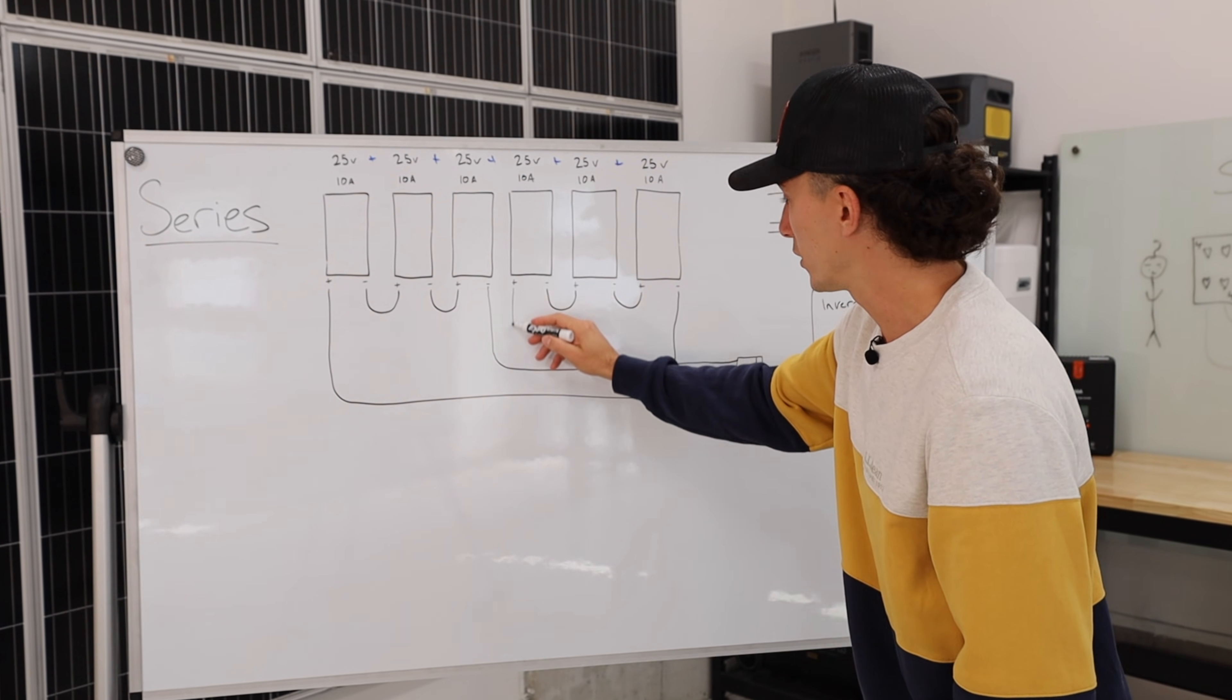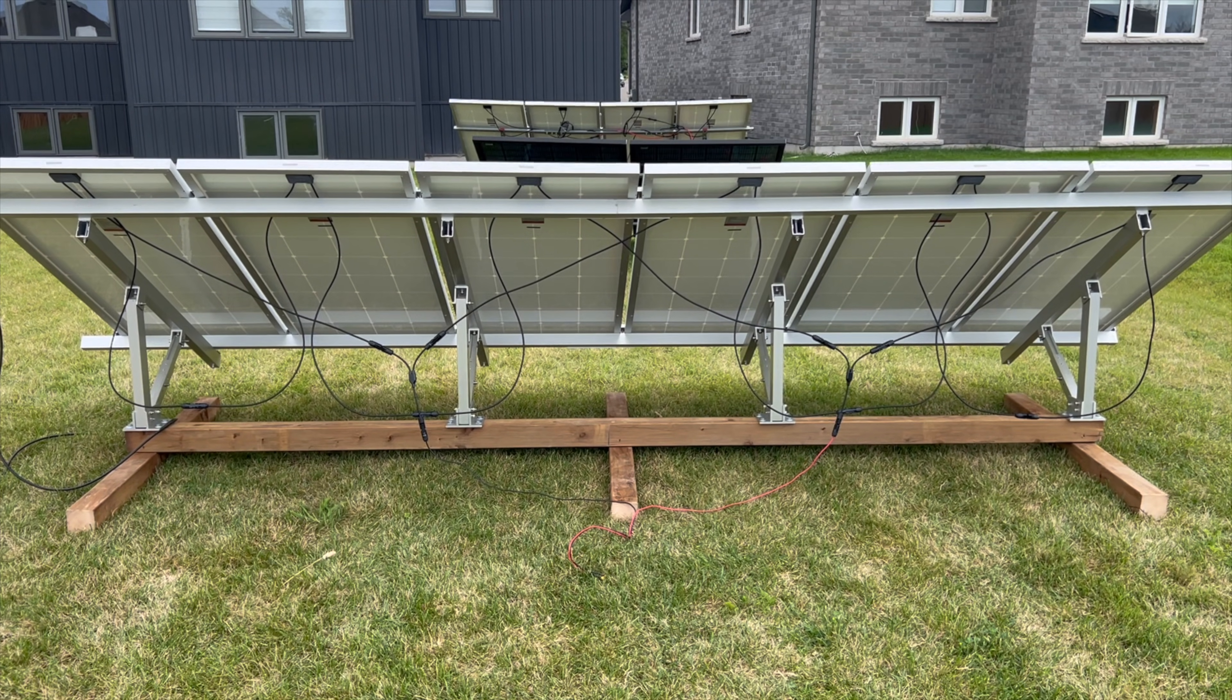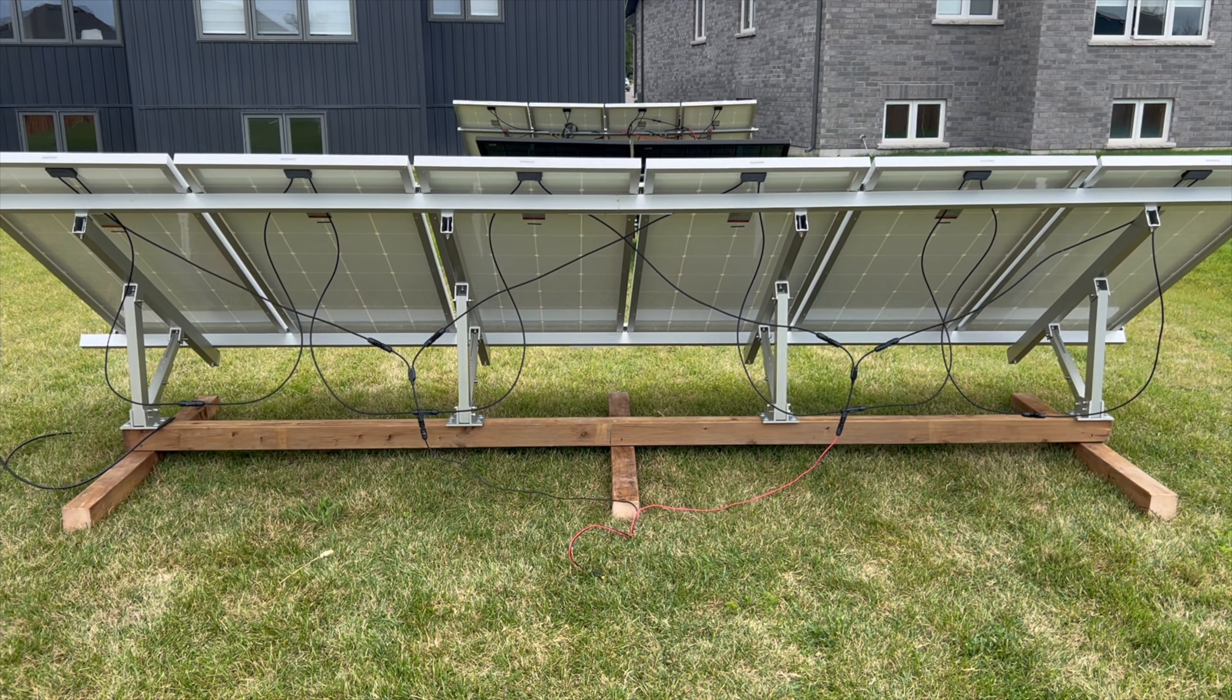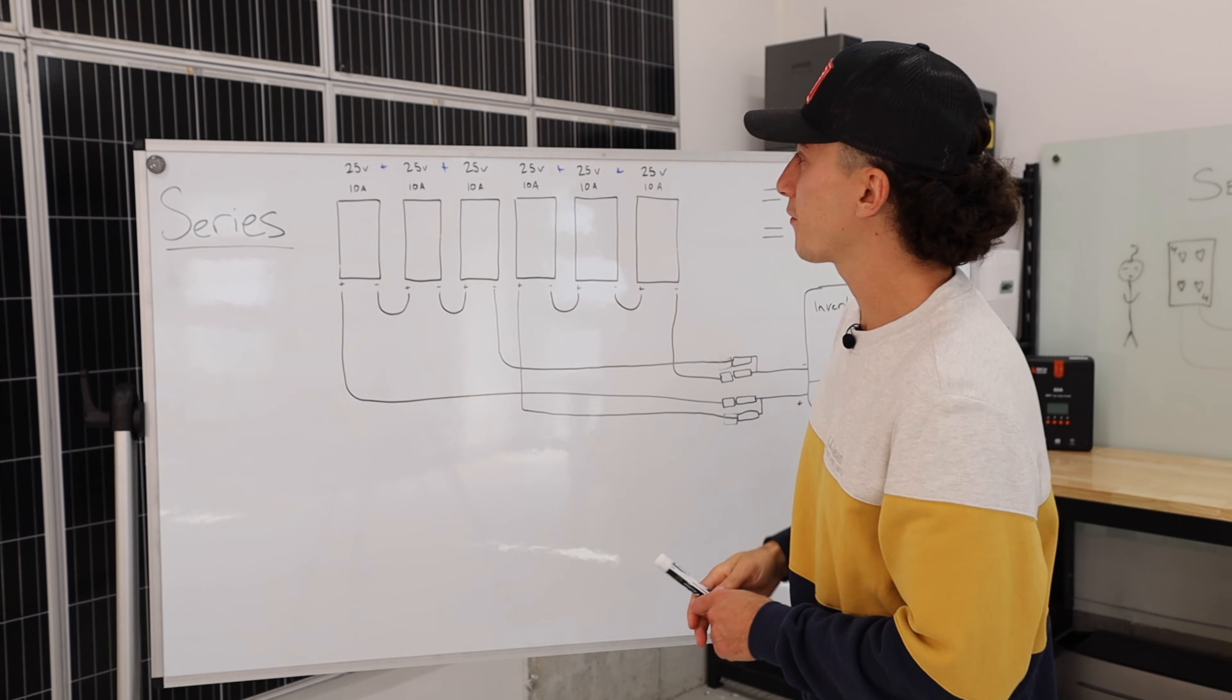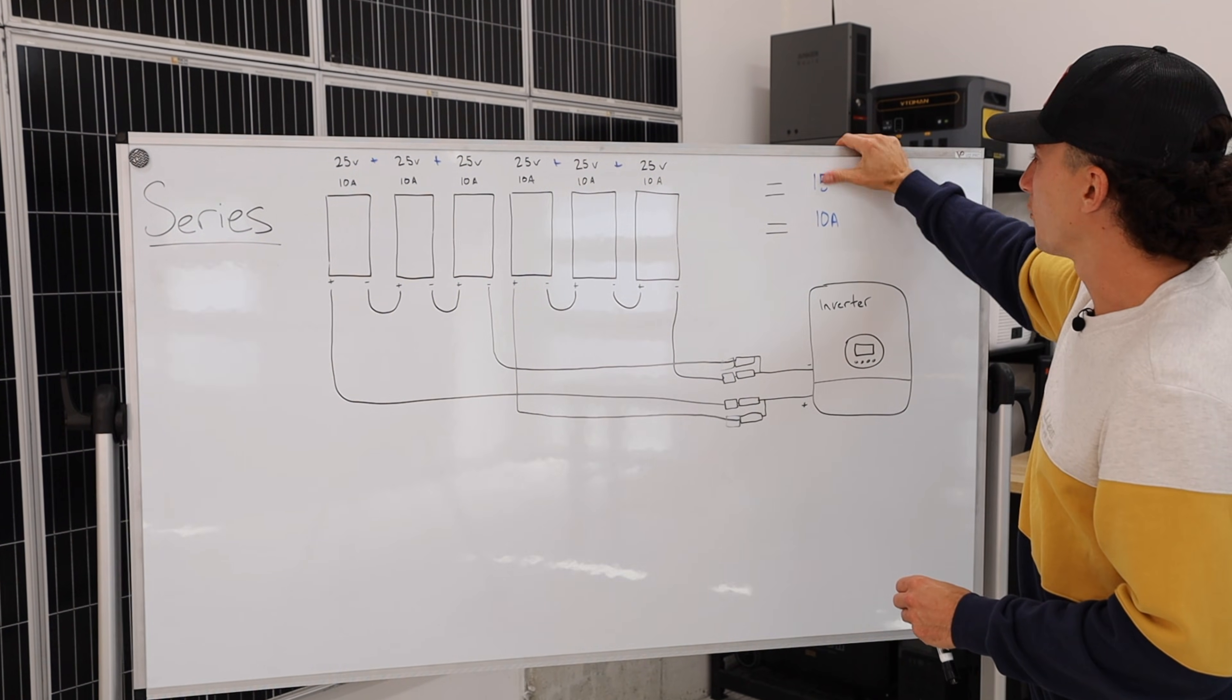Now you have two strings, two different input strings of three panels. So now you would break that in half, you add 25 plus 25 plus 25—the maximum voltage that you're going to have with this setup is going to be 75.